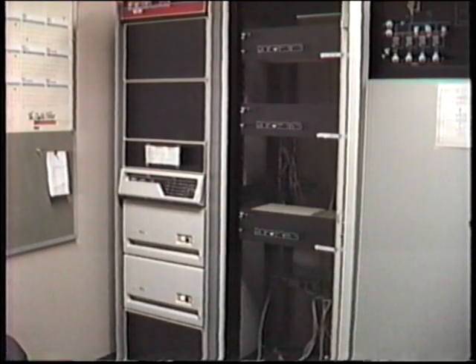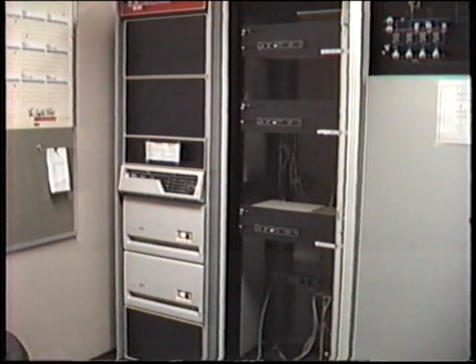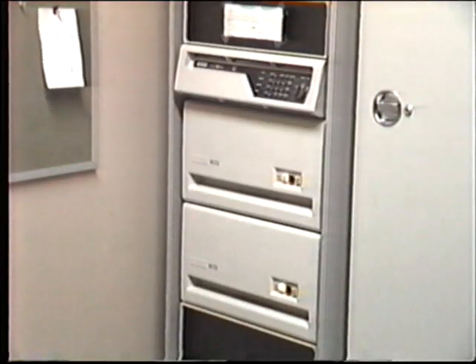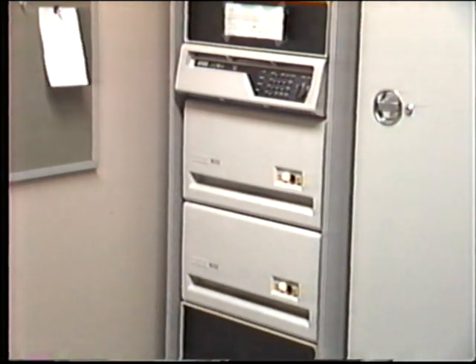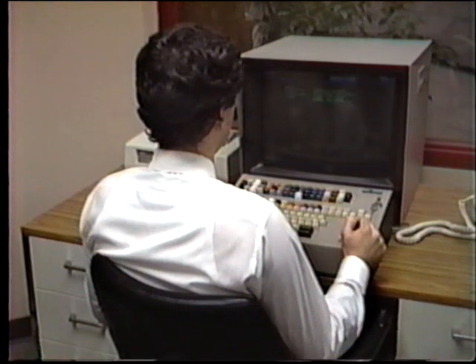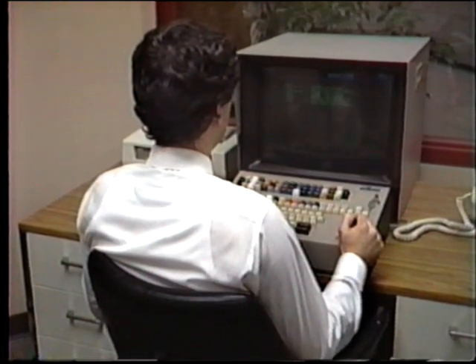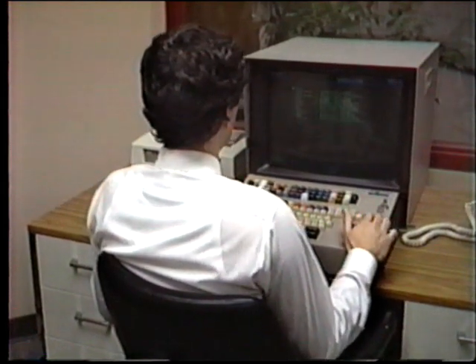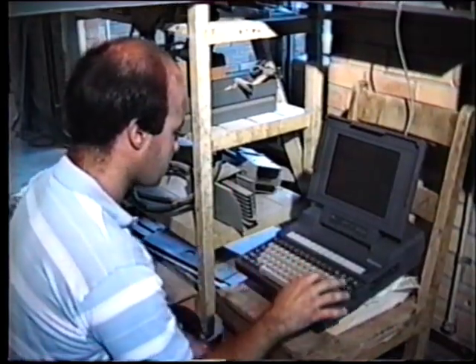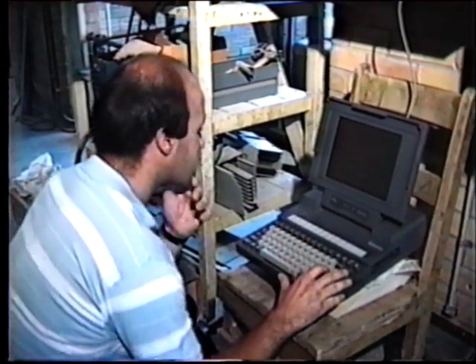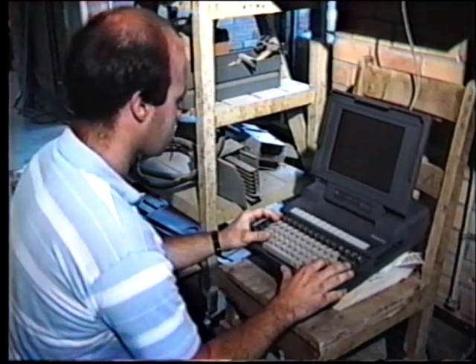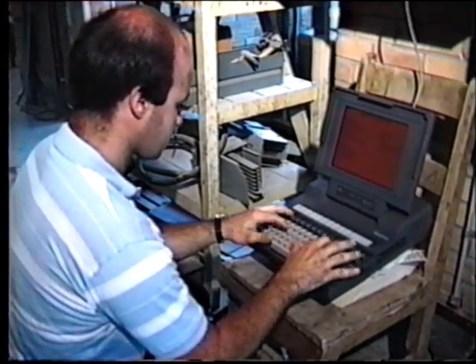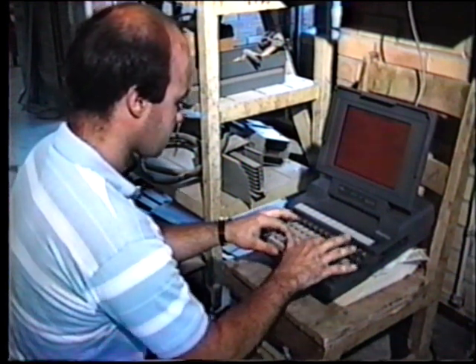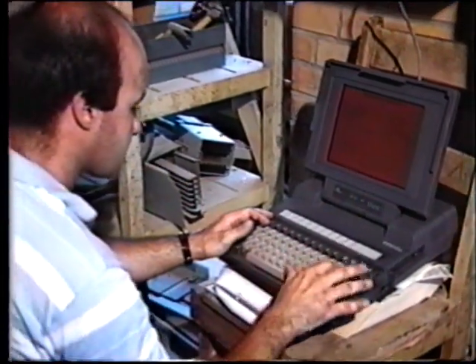Such signals can also be transferred by modem to a central computer located at a remote location, say the main engineering office or operational center. This facility also offers the ability to reprogram the relay settings from the remote terminal. However, this is more likely to be performed locally. In this case, a small personal computer would be connected into the relay at the appropriate input. Some of the more recently manufactured digital relays are making this programming activity more user-friendly. Instead of having to resort to computer language, the relay technician and engineer can choose from a menu of conventional terms with which they are already familiar.